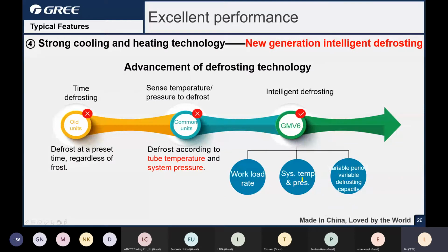Next one is about the defrost. Defrost is a common problem for air conditioners in heating mode during the winter. The outdoor units will accumulate a lot of ice, so the units have to run the defrosting logic to eliminate the frost. For the older units, the defrost depends on the running time. It's fixed: after running for so long, it starts the defrost. It's very stupid. The common units will detect some parameters such as the temperature and pressure.